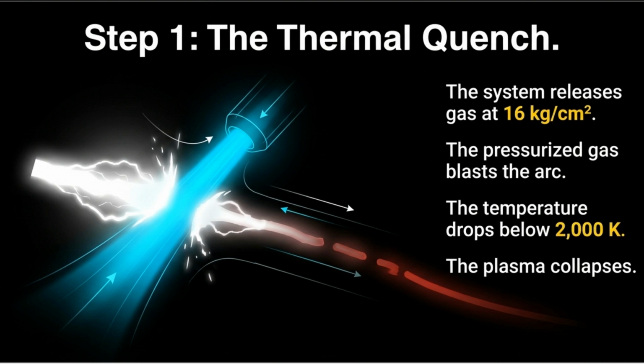Step 1 is the thermal quench. The system releases gas at 16 kilograms per square centimeter. This pressurized gas blasts the arc, dropping the temperature below 2000 Kelvin, causing the plasma to collapse.